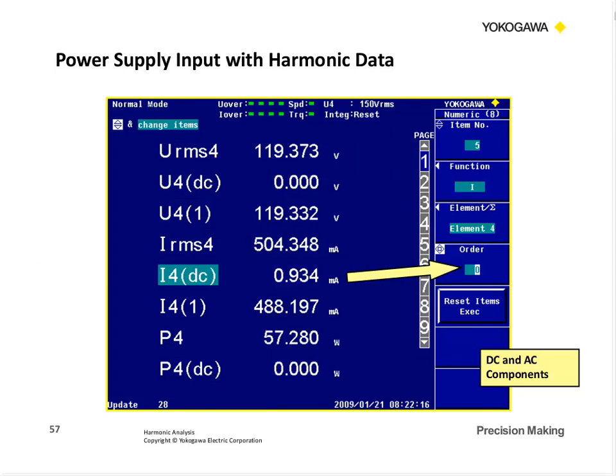So if we look at our same old power supply, here we're looking at the RMS value, and 4 just happens to be what channel it's on, so don't get confused with that, but it's the RMS voltage. Here's the DC voltage component. Okay, there was no DC on this particular waveform. And then we can go in and break it down to the harmonic order, and this breaks it down to order number 1. So this is the true RMS value, which includes all the harmonics that are available to measure with that RMS calculation formula that we use. True RMS measurement. This is just the fundamental.